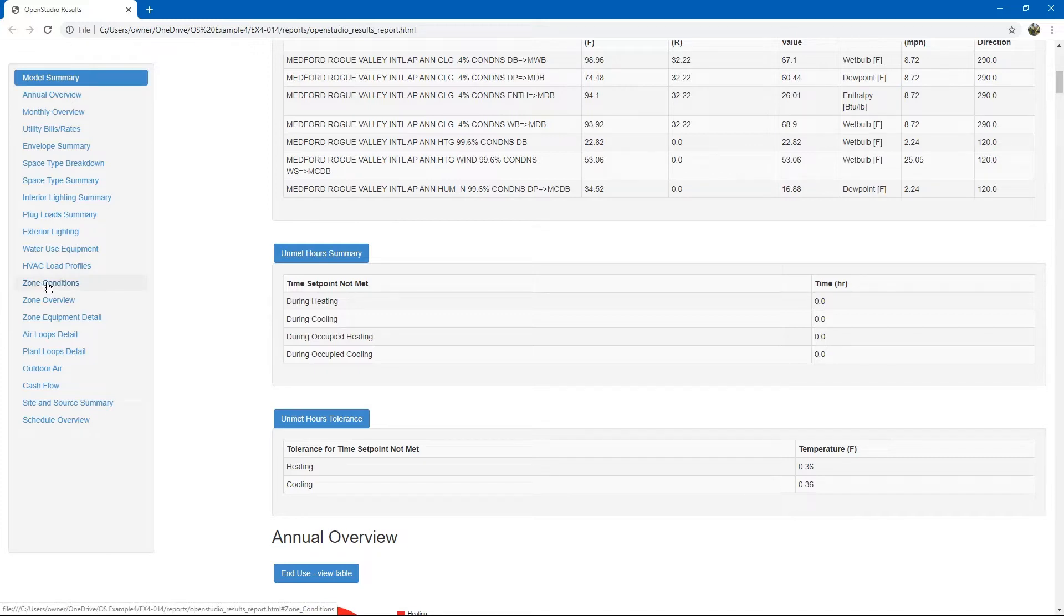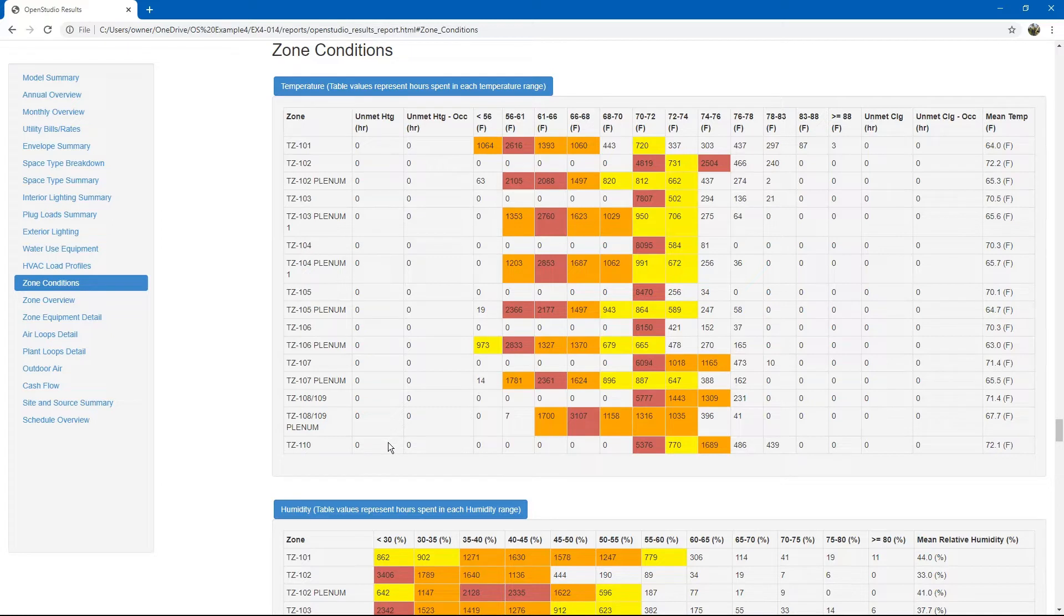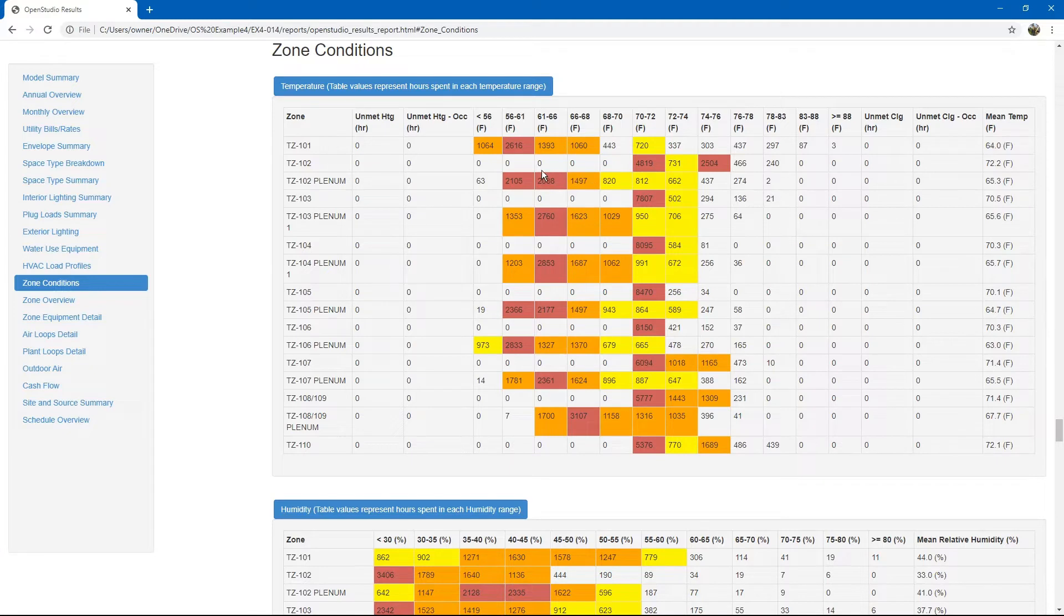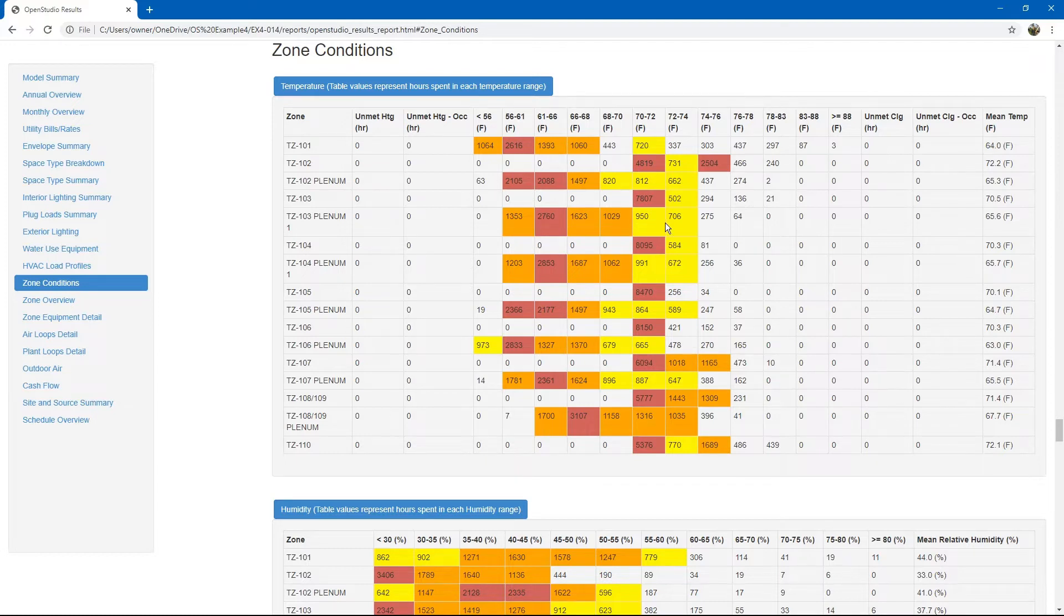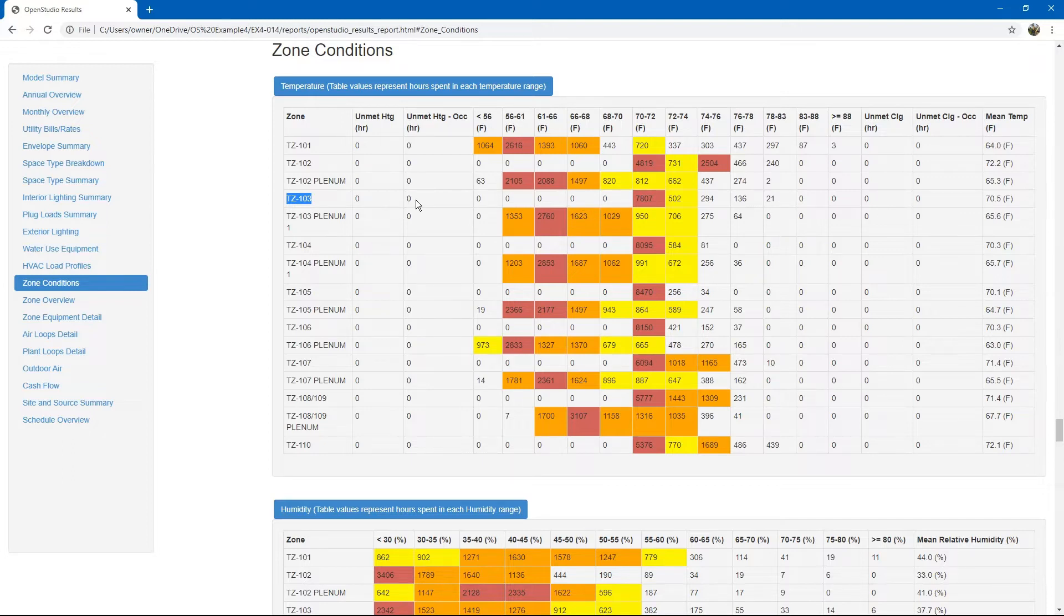Click the zone conditions in the table of contents on the left. Here, you can see unmet heating hours on the left and unmet cooling hours on the right. This table shows you a range of temperatures that the spaces experience throughout the entire year. If some of the spaces, for example thermal zone 103, fall below the heating set point for a certain number of hours, that is considered an unmet hour, especially if it is an unmet occupied hour.